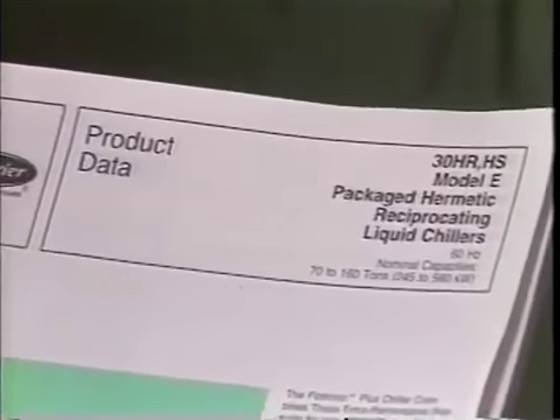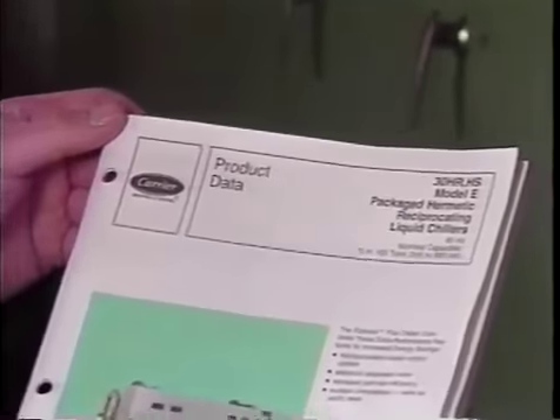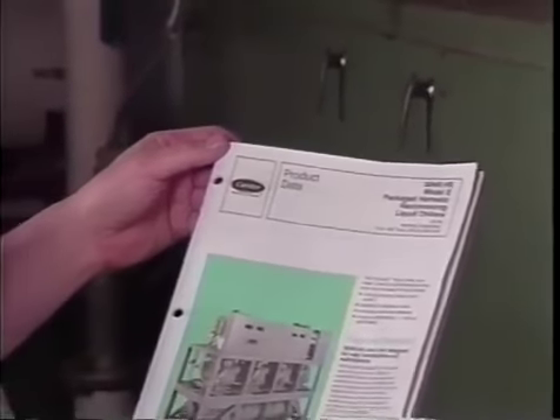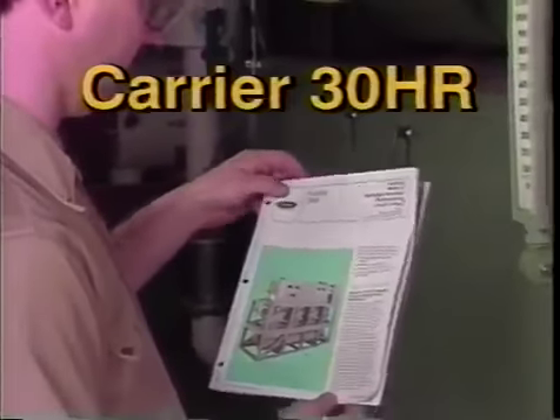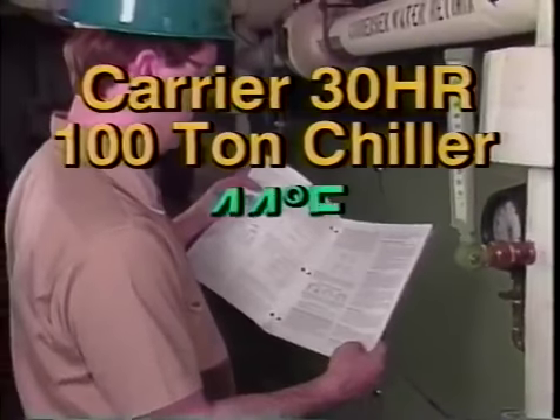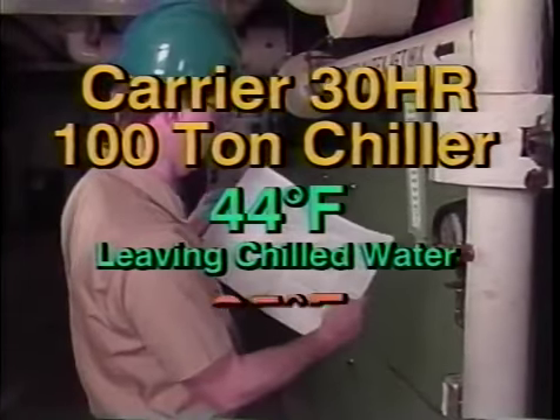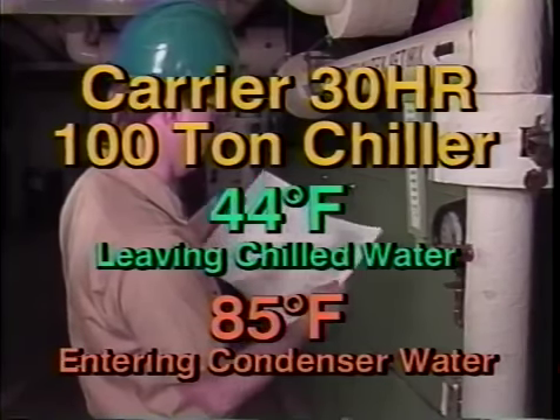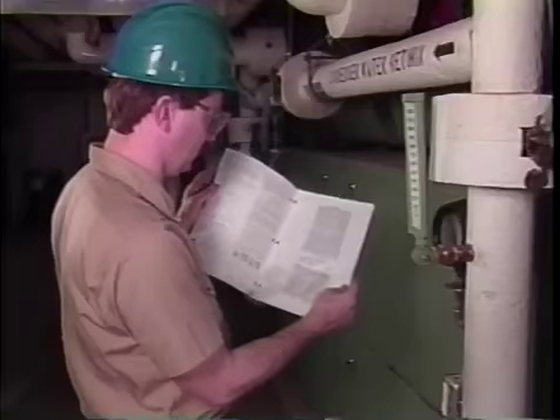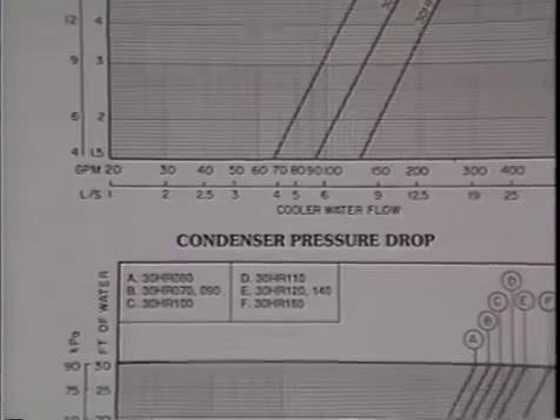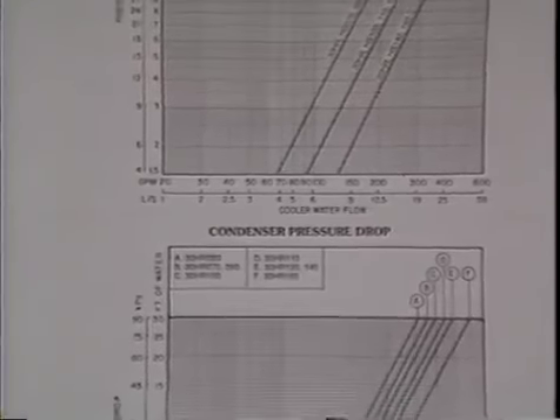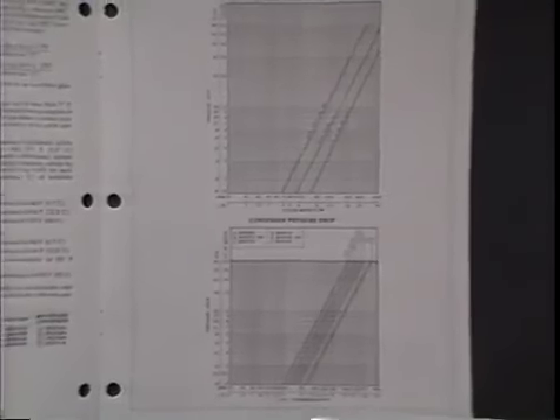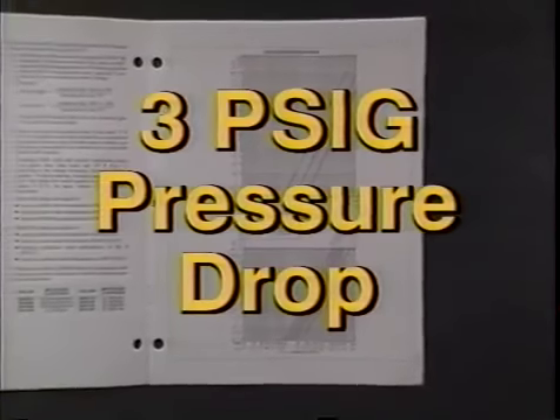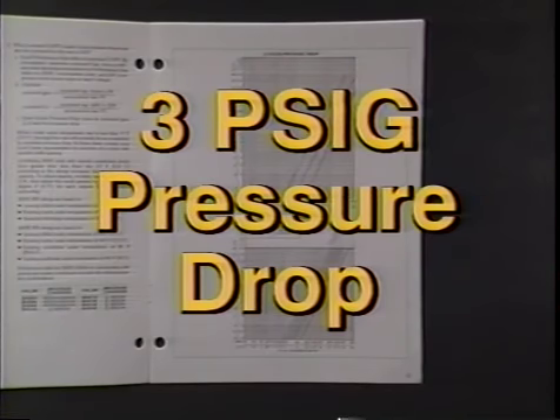To determine proper water flow, you should be familiar with the manufacturer's product application data. For our example, we'll use the application data for a Carrier 30HR 100-ton chiller with 44° Fahrenheit leaving chilled water and 85° Fahrenheit entering condenser water. The manufacturer's application data will provide you with the pressure drop information needed for troubleshooting. These pressure drop GPM charts can be used to compare the actual flow to the design flow. For example, if we have a 3 psig pressure drop between the inlet and outlet of the condenser, we could verify the flow rate using the following procedure.